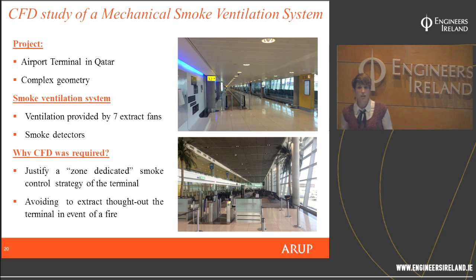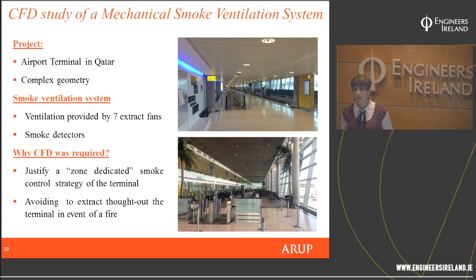A project example of how CFD helped push design to the limits was an airport terminal in Qatar, with a walkway extending up to three kilometres. Following prescriptive codes would have required compartmentation every so often, dividing the three kilometres into smaller areas with significant concerns around structure, ventilation, evacuation, and escape routes. CFD was used to justify an open-plan area with fewer evacuation routes and an optimised ventilation system.